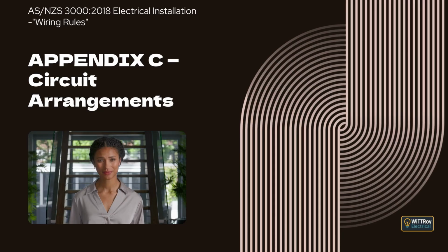Clause C 2.4.4, Alternative method using switchboard diversity. This clause explains that for switchboards conforming with the AS/NZS 61439 series, maximum demand may be determined by applying a diversity factor to the sum of the circuit protective device ratings. The diversity factor depends on the number of downstream circuits and reflects the reduced likelihood of all circuits operating at full load at the same time.